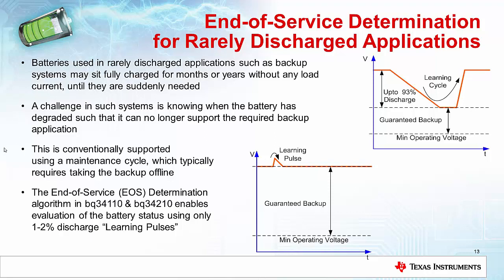Conventionally, this is done by running a maintenance cycle. This is usually done by taking the system offline, discharging some significant portion of the capacity of the battery, and then recharging again to do a maintenance or learning cycle. If you do this by taking the system offline, you have to have a spare backup system to keep the system backed up during that time, or you accept that you have less guaranteed backup while doing this maintenance cycle than at other times. If I was in the middle of a maintenance cycle and right then I had an emergency, I would have much lower capacity available for servicing the emergency than I would otherwise.